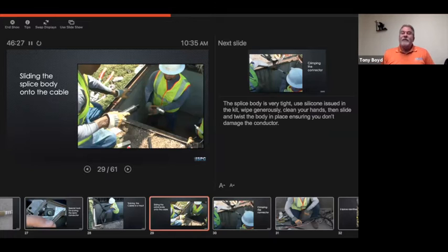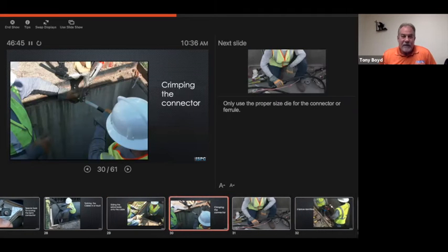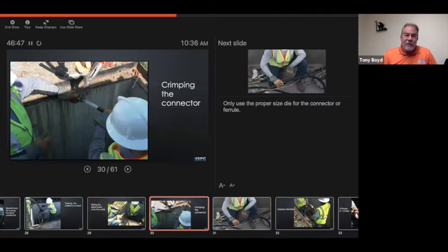They get contaminants on the gloves, and then they grab the splice body and go to sliding it on, and before you know it, we've got contaminants on the cable itself. So I always had my guys clean their hands and use bare hands when putting the splice together or sliding a terminator elbow or a terminator onto the cable. So, to each his own, whatever company chooses to do.